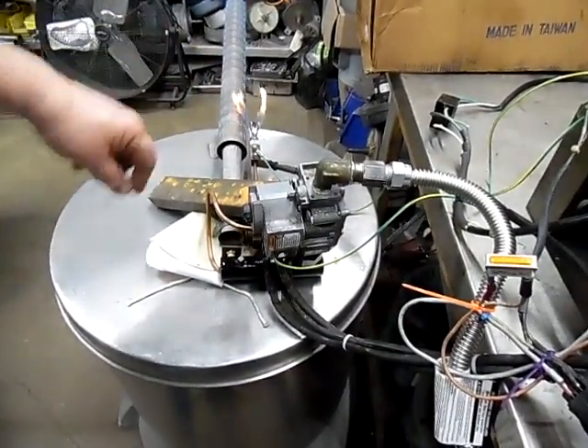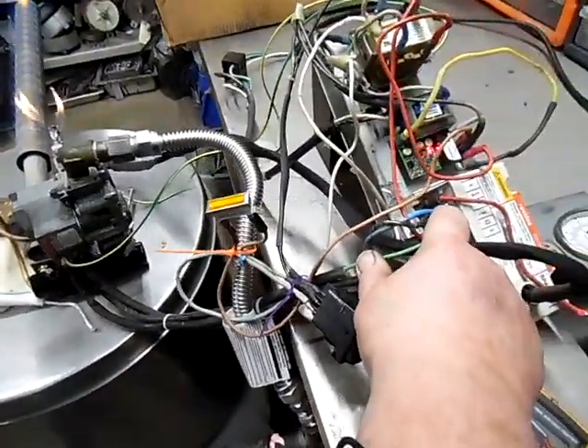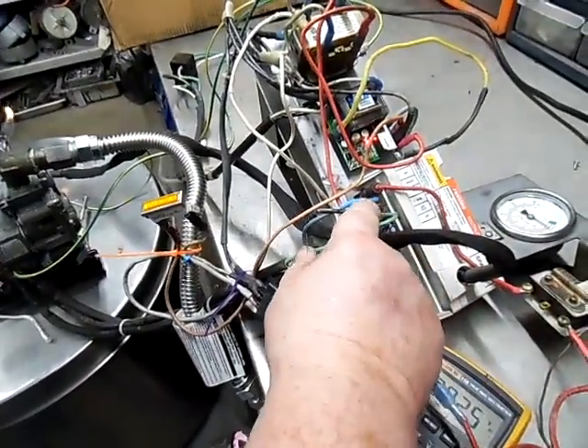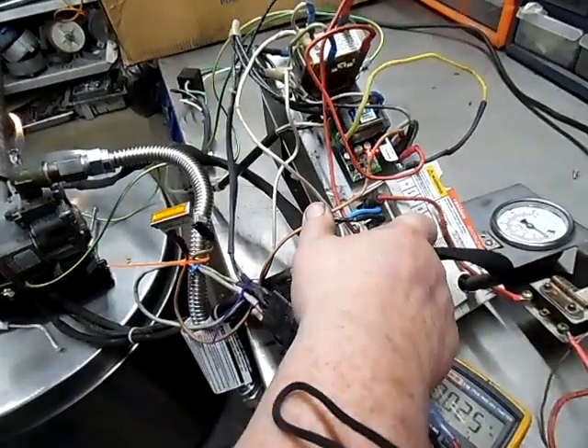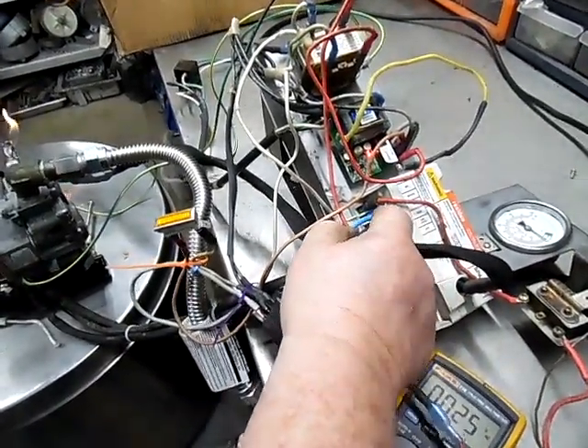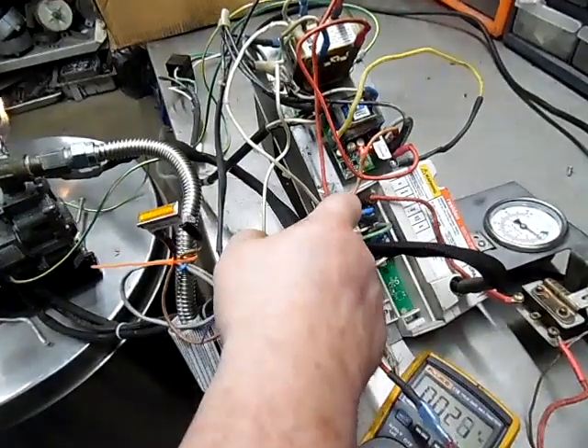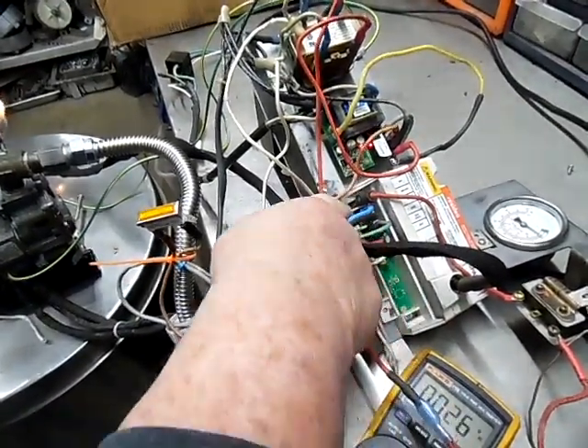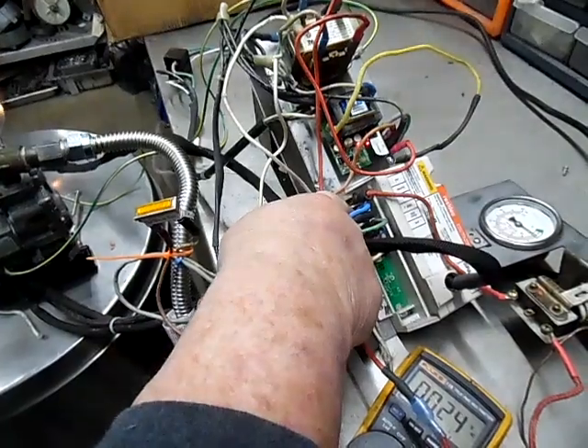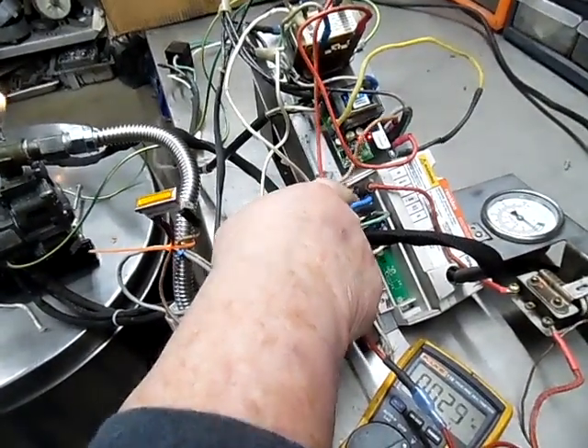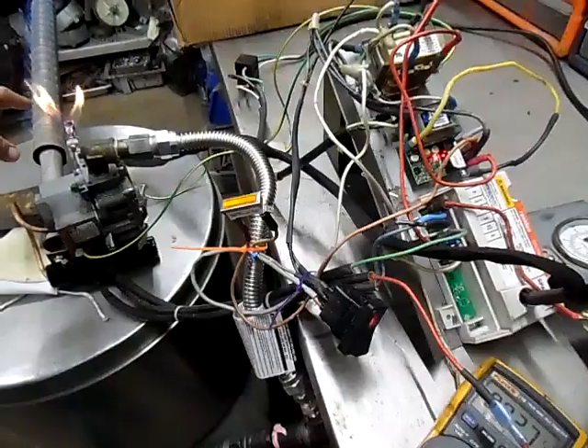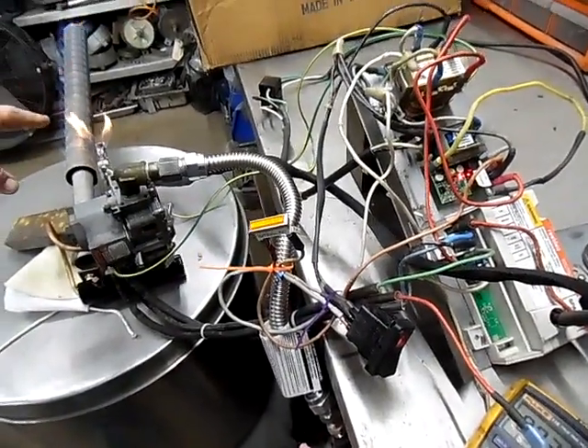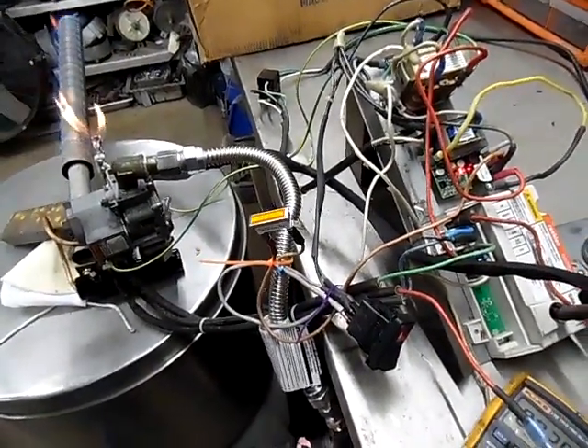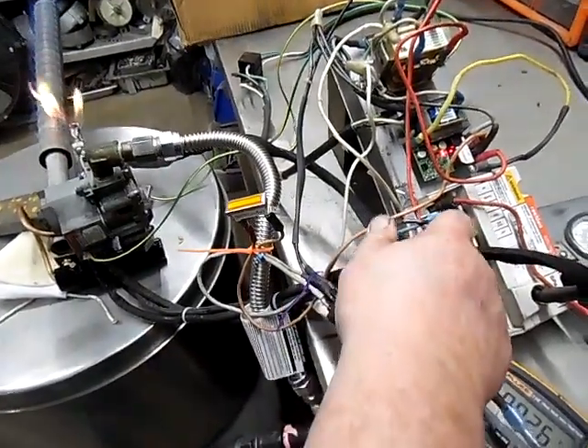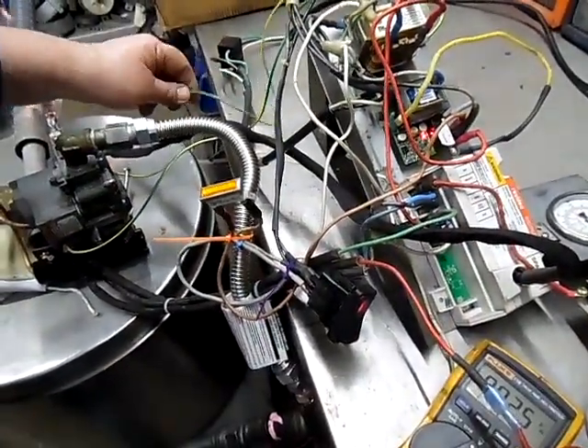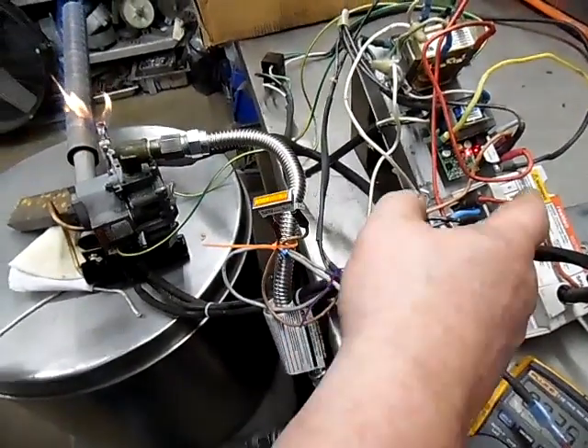So again, you can check backwards. If you're not getting the spark out of your box, make sure your box powered up. Once you have spark out of your box, you want to make sure you have gas at your gas valve. So you check across your PV and your common, which is your MV/PV, and you should have 24 volts going to the valve, which ignites the pilot. Once that pilot lights, within 1 or 2 seconds it should turn on the main valve, and then you'll get flame out of the main burner. This is why I say, if this doesn't read the proper reading off this flame rod, it will not turn on MV.